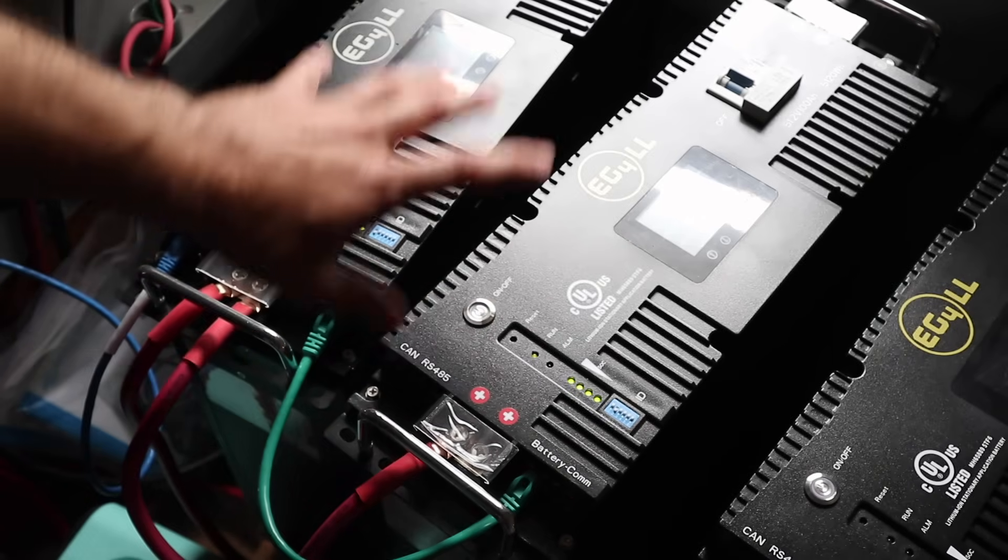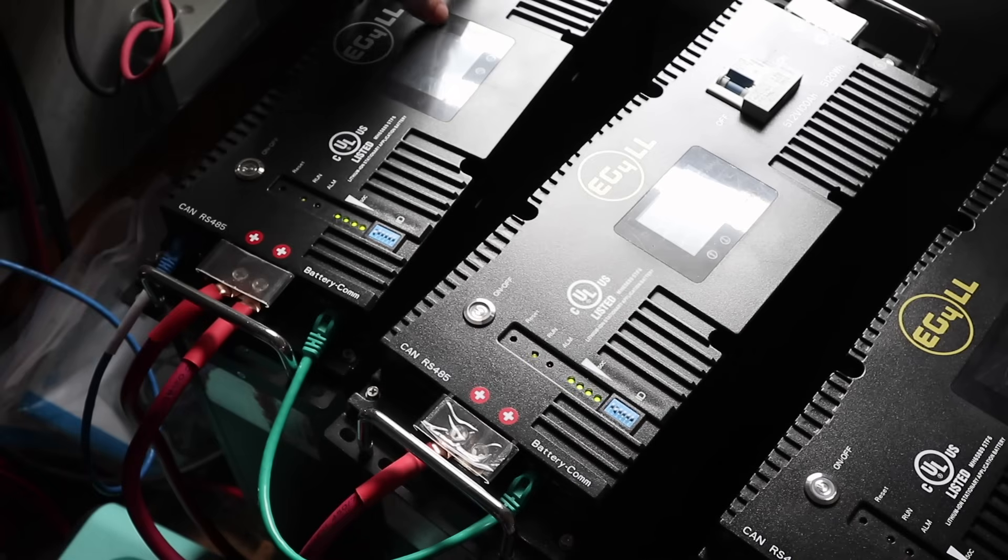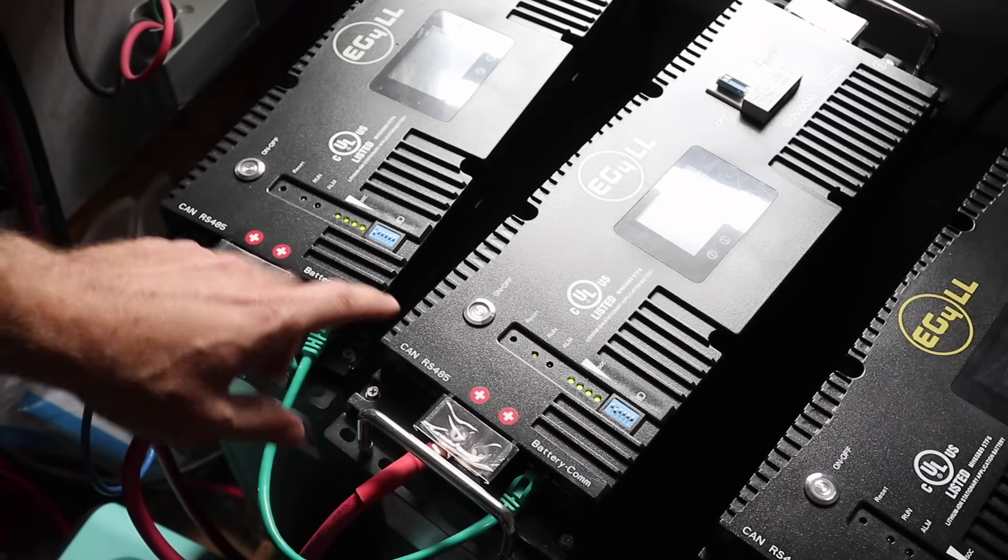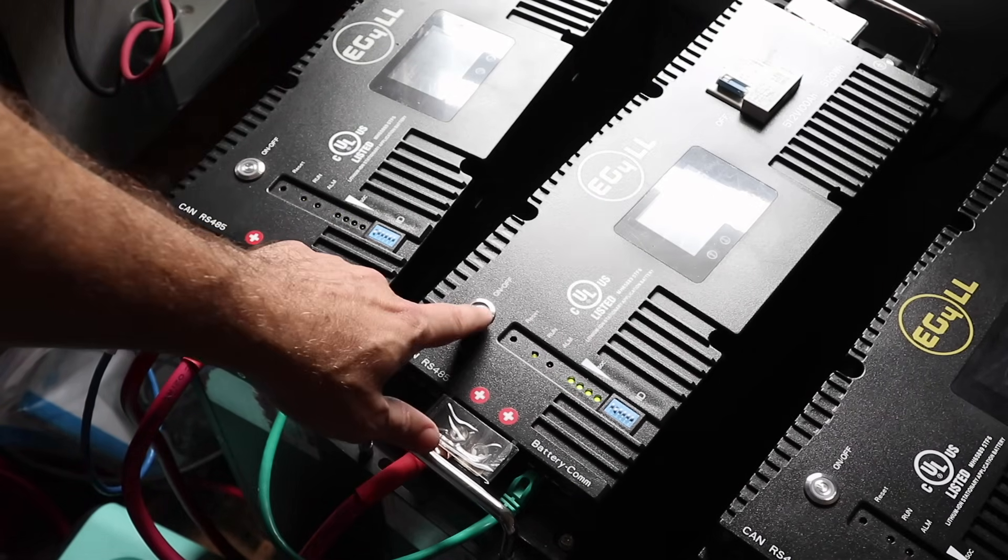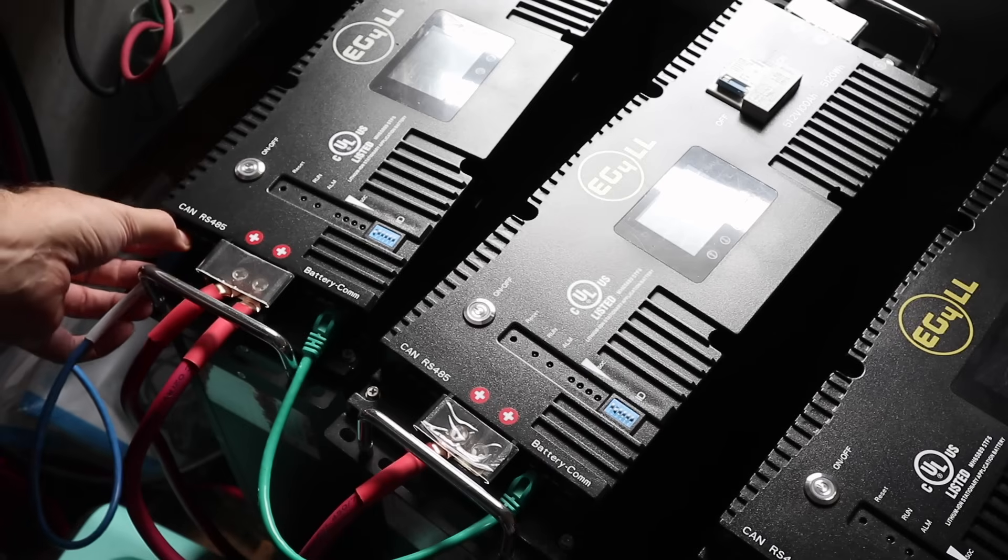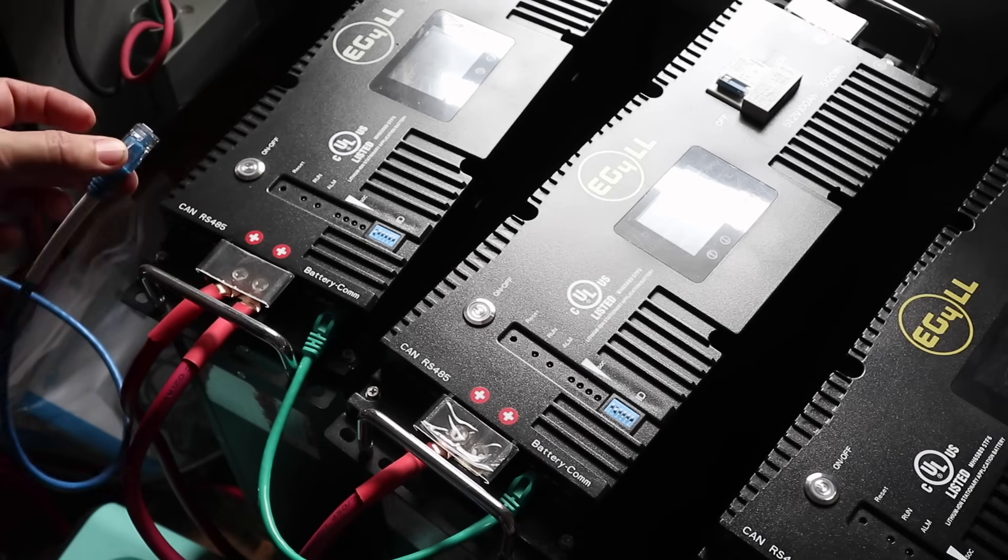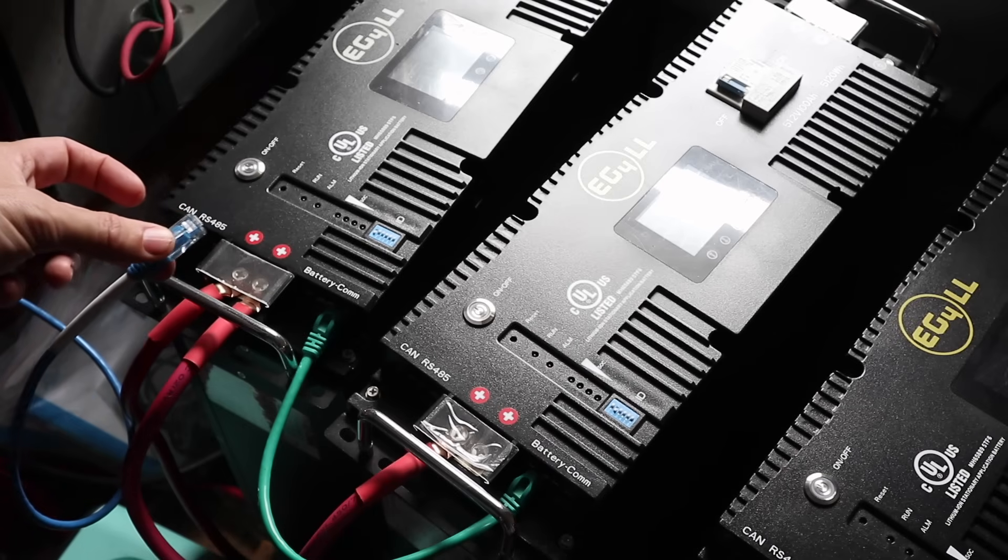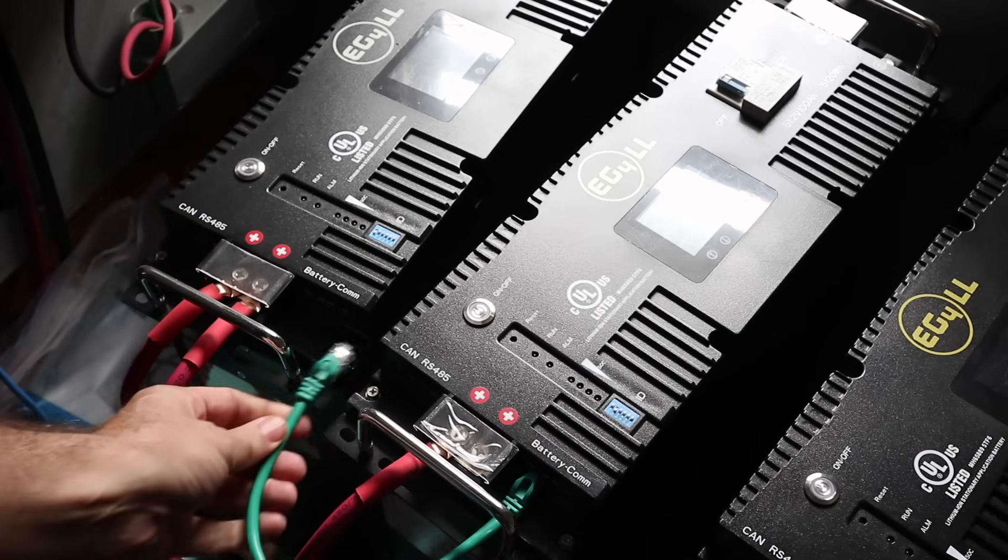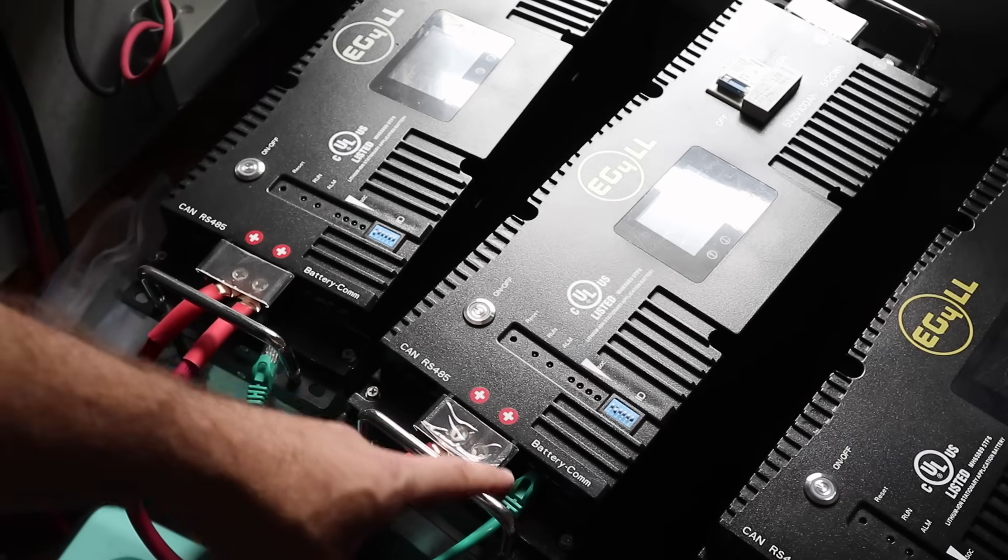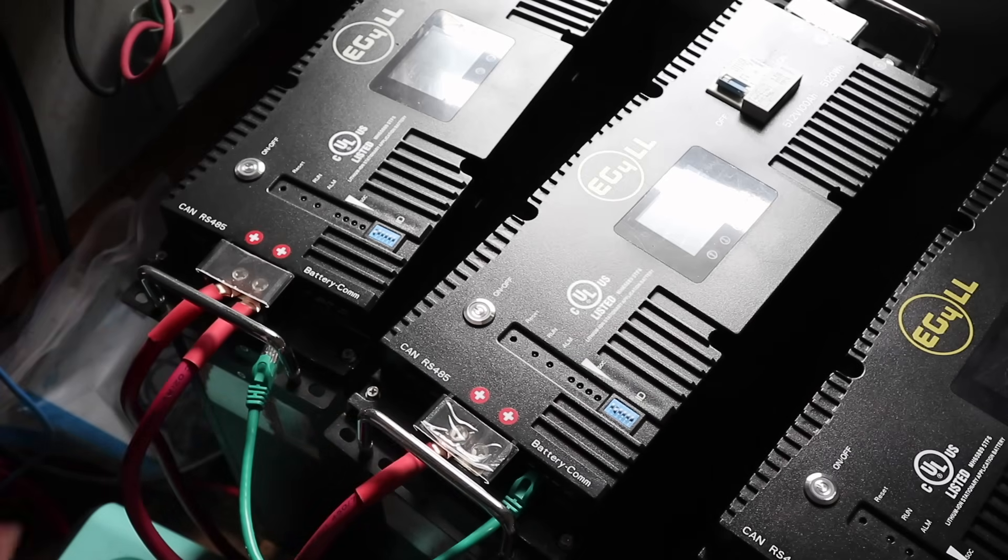So we're going to first turn off the breakers on our batteries, and then turn off the BMS on each battery. We're going to disconnect communications from the inverter, and then we're going to disconnect communications between the batteries themselves.